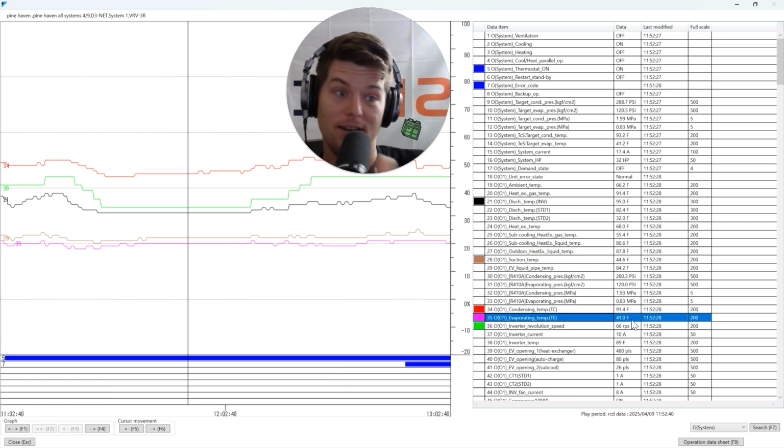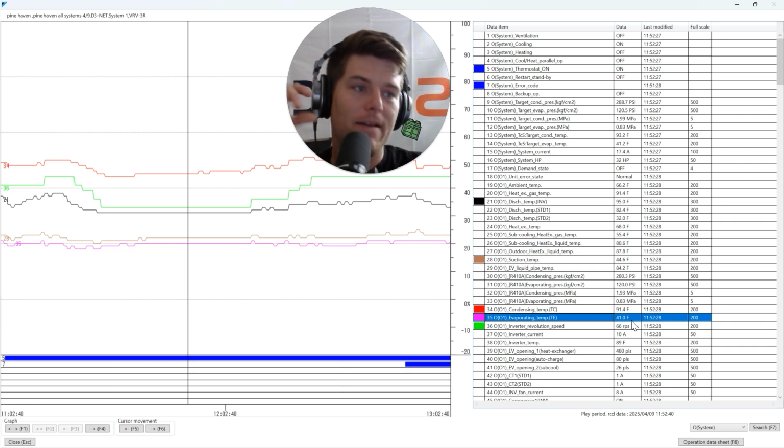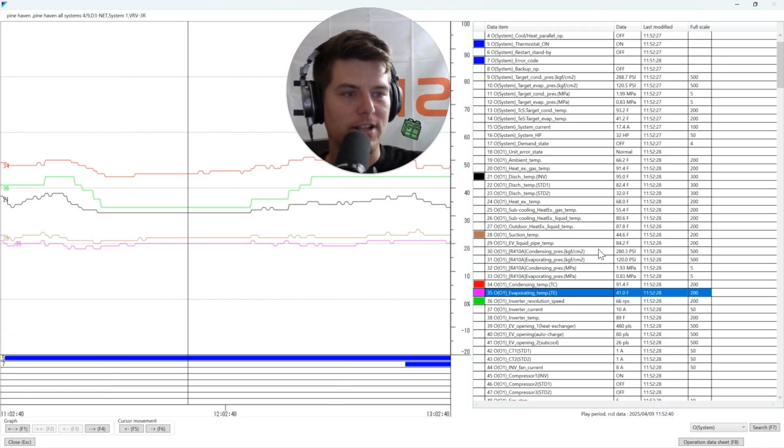So this is bad. This is a very low suction superheat. And then how do I know that it's compressing liquid again? Because my discharge superheat is 4 degrees. Give that compressor a break. 32 is the lowest I want to see it, and I'm at 4. Yeah, so she's probably shaking like a paint shaker, but that's okay because we're going to save the day here.